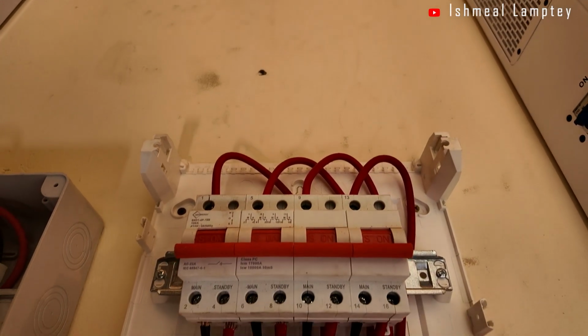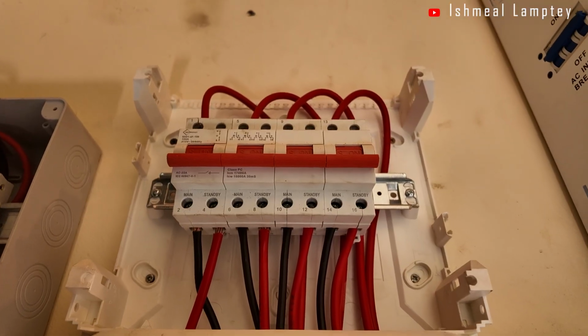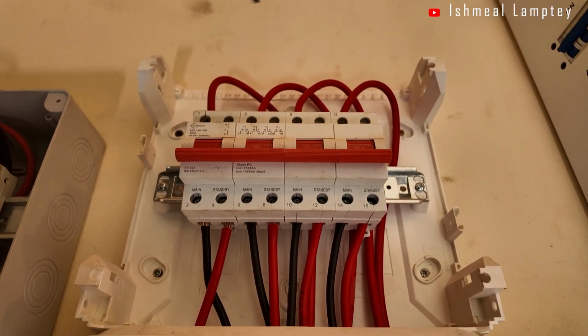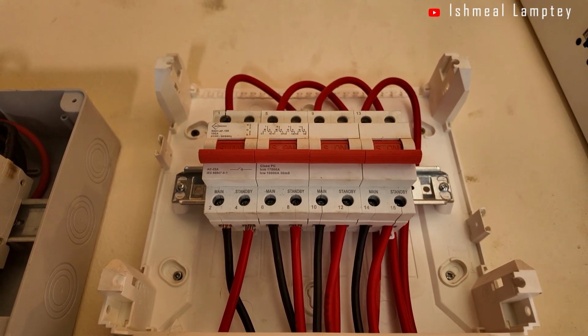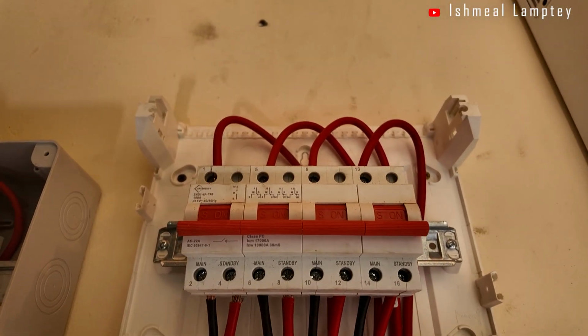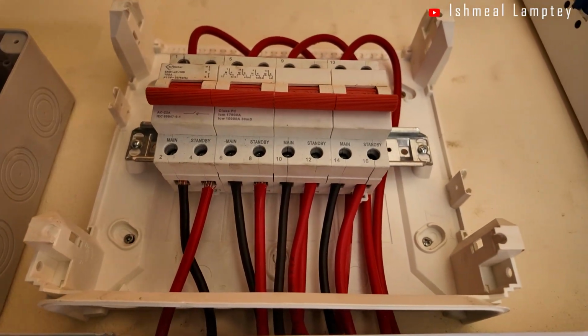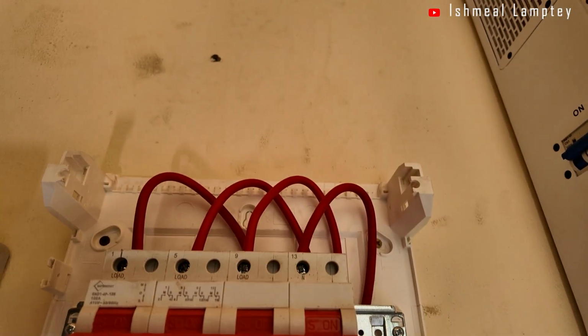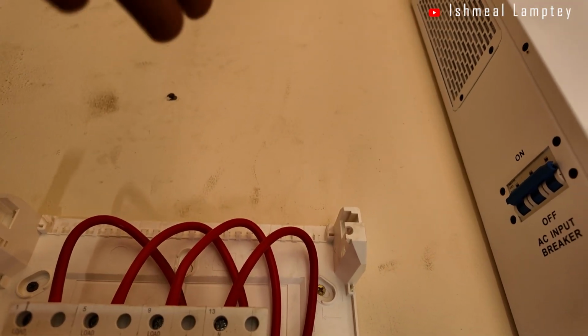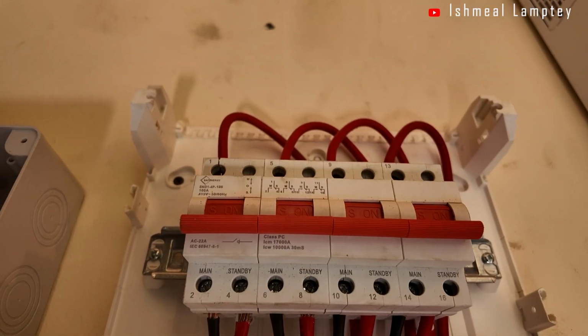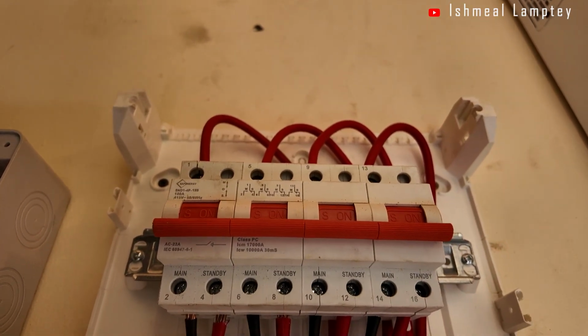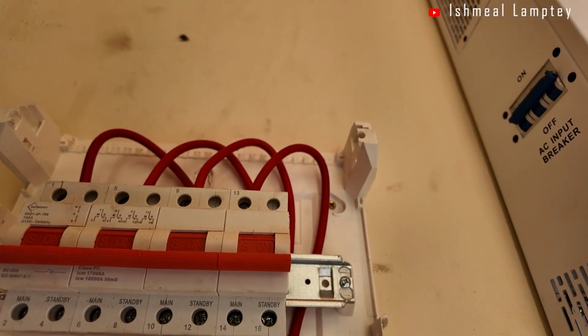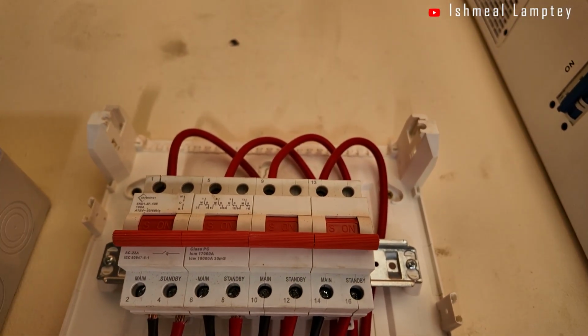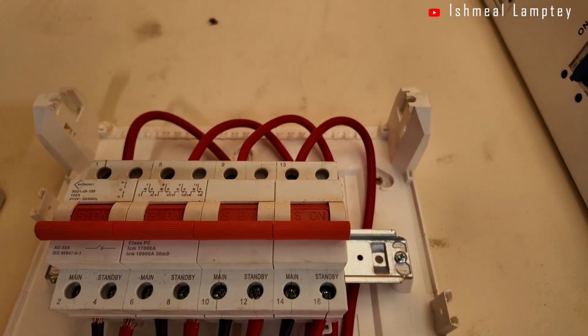Then you come to the changeover. We used the breaker-type changeover. There are different kinds of changeovers available: automatic ones, manual ones, among others. What we used was a manual one, but it's the breaker type. It has 3 levels. It has the off mode, which is the middle point, the grid mode, and then the other power option mode, being solar, a generator backup, among others. For ours, we put the grid power at the top. So once you switch to the very top, that means you're using grid.